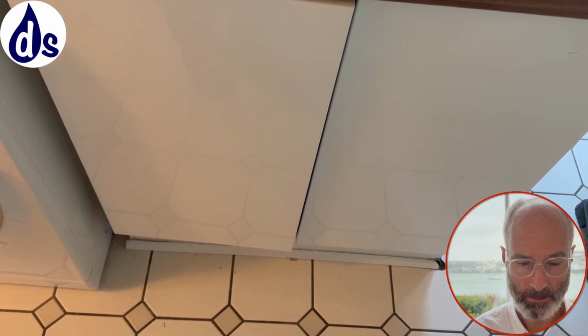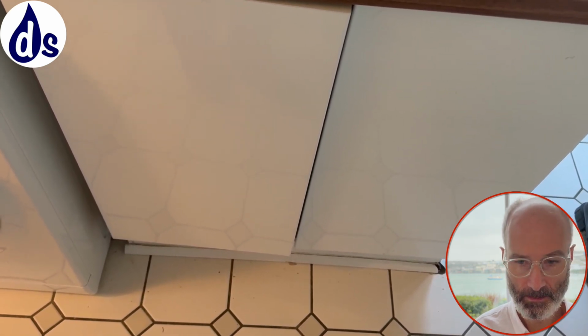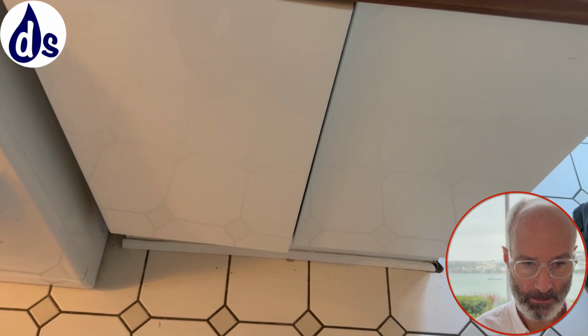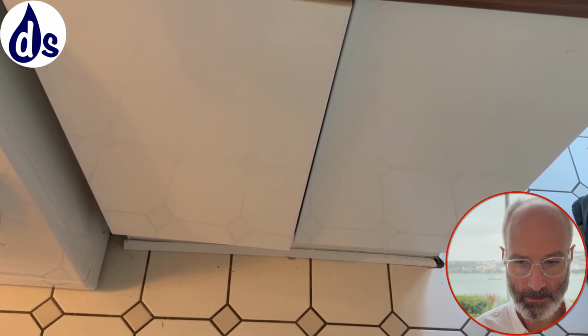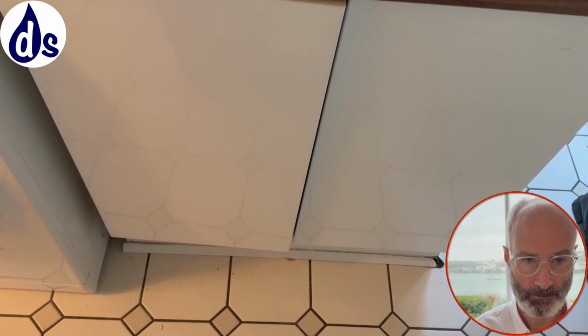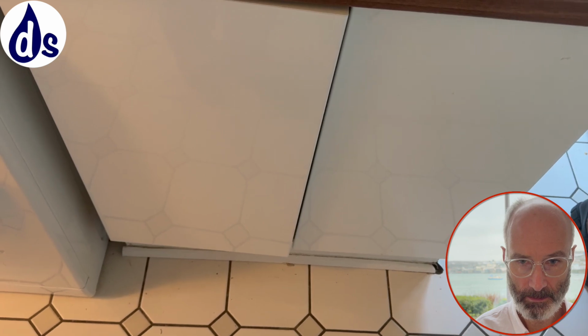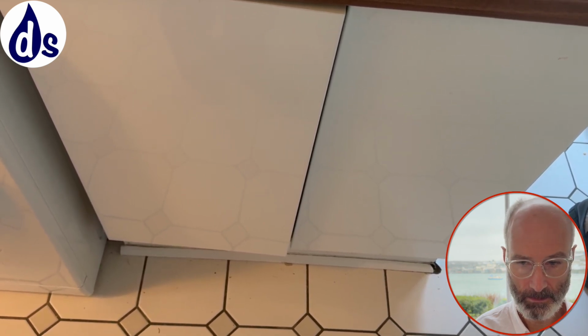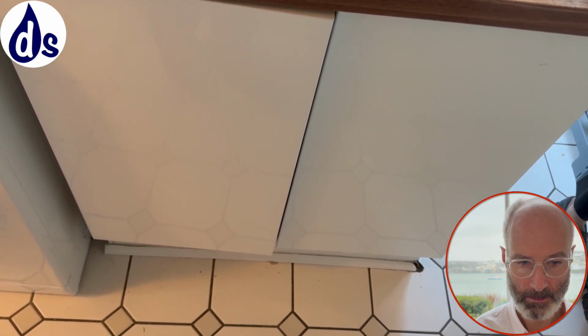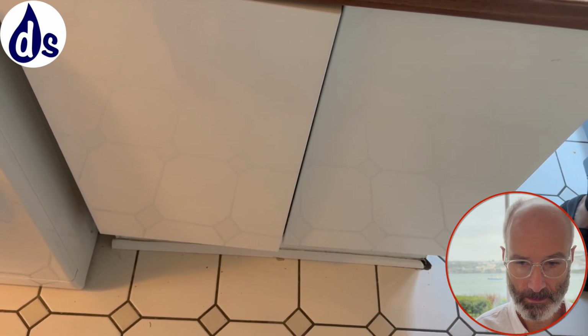You only need heat loss and that kind of thing, I presume. So for all the air that you're blowing out, you have to replace it with cold air from the outside, which needs heating. For a continuous flow bathroom extractor fan running at 5 litres per second, it costs about £200 a year of additional heating costs for heating that up. If you use a dehumidifier, all the energy that's used in the dehumidifier comes out as heat. Plus you get a 50% bonus through entropy, because it's moving from the vapor phase to the liquid phase. It's a bit like an air source heat pump. It's reducing vapor, it's releasing heat.